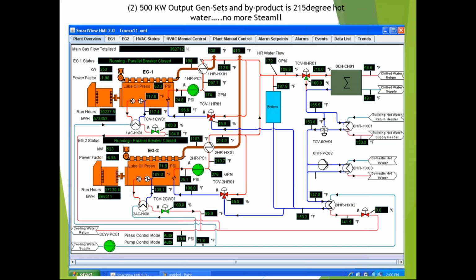That's critical because my target for the cogen jacket water is anywhere between 210 to 215. I need that. I can't do anything else less than that. Then I get reduced. That 210 is the energy source for an absorber chiller. That's key, right? Because I need chilled water 24/7.